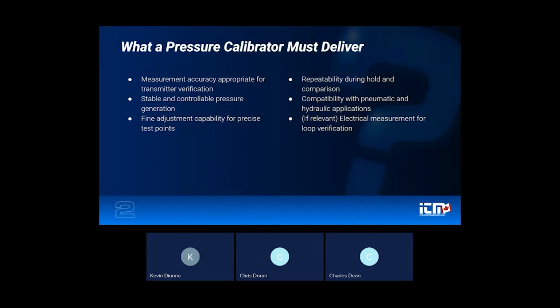Repeatability is equally critical. I just went over that. But during calibration, pressure must be applied, stabilized, and compared consistently, once again, across multiple test points. If the source drifts or fluctuates, it introduces uncertainty that has nothing to do with the device under test. Finally, in many field applications, electrical measurement capability is also required. So when verifying pressure transmitters, technicians also often need milliamp output as well, simultaneously controlling pressure, ensuring both the mechanical and electrical sides of the loop are performing as expected.